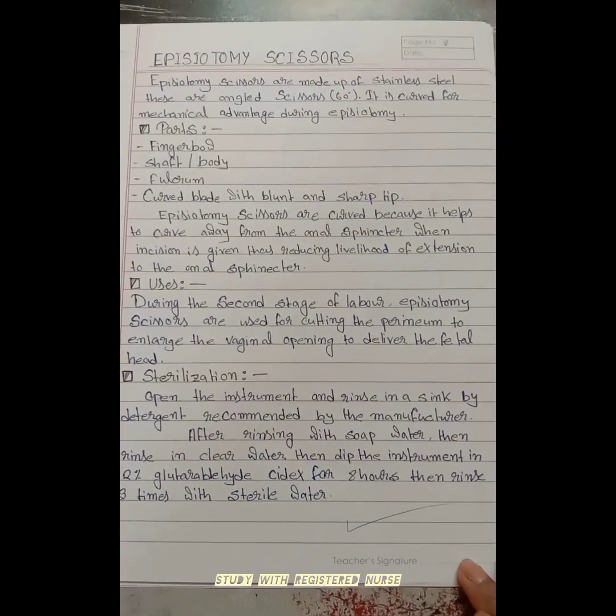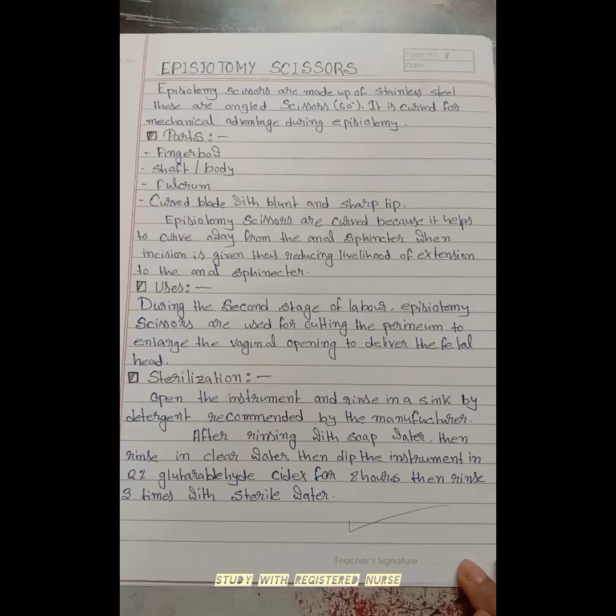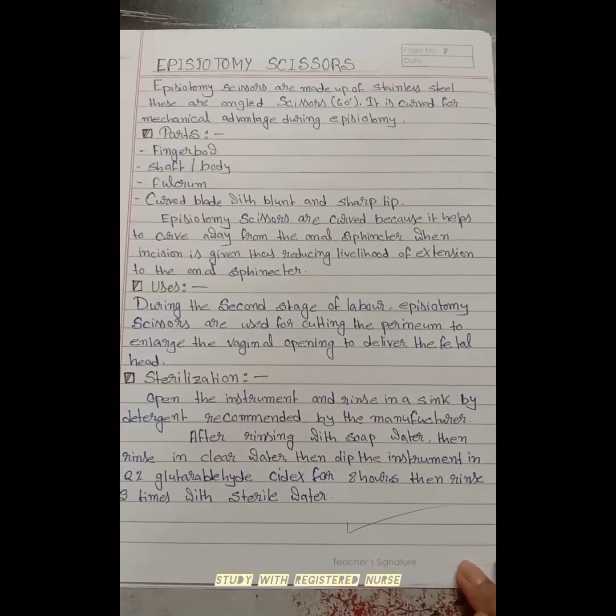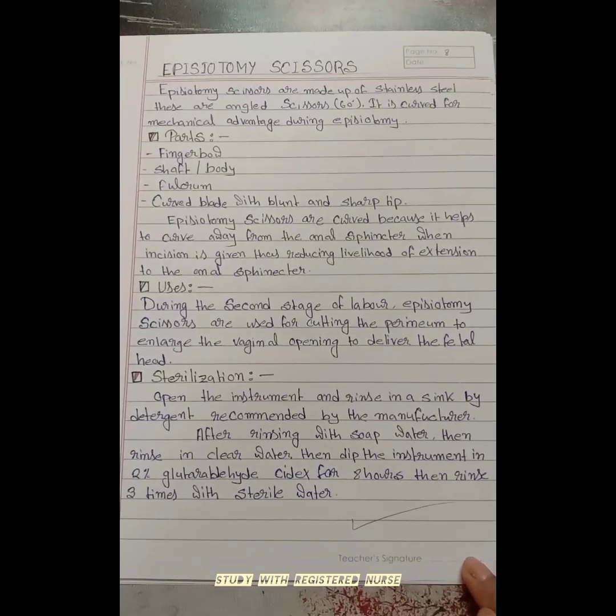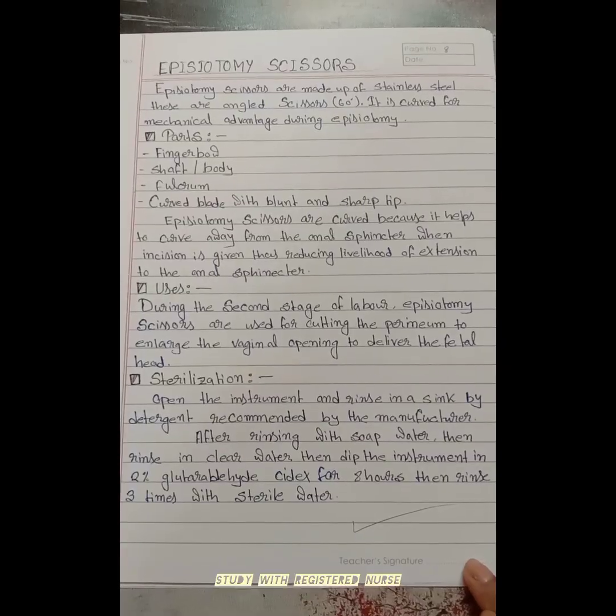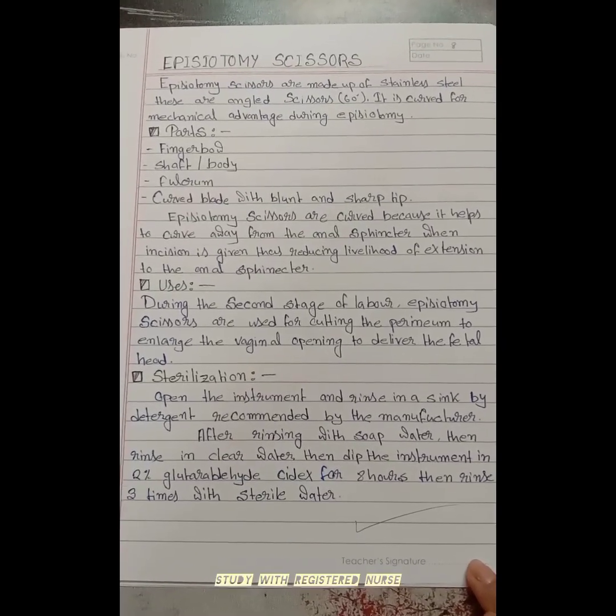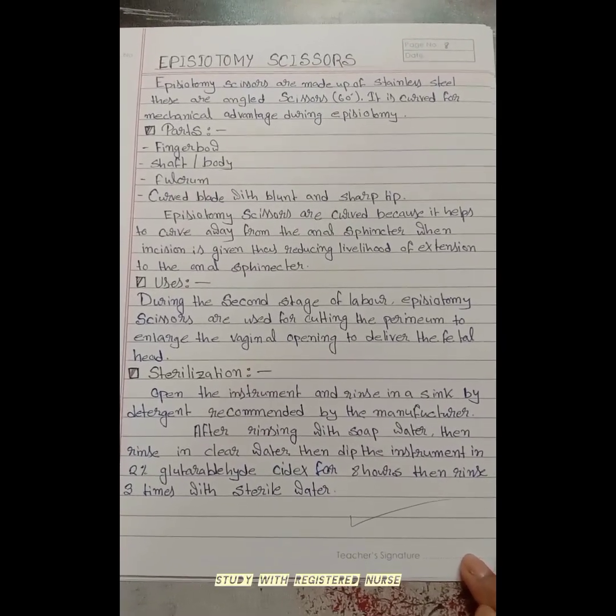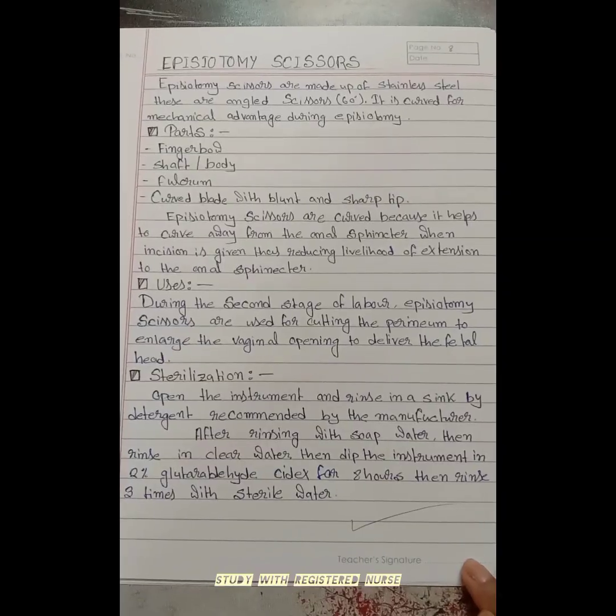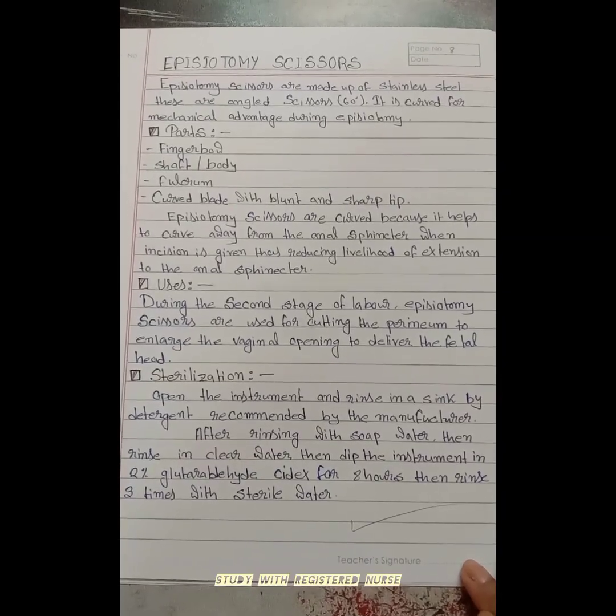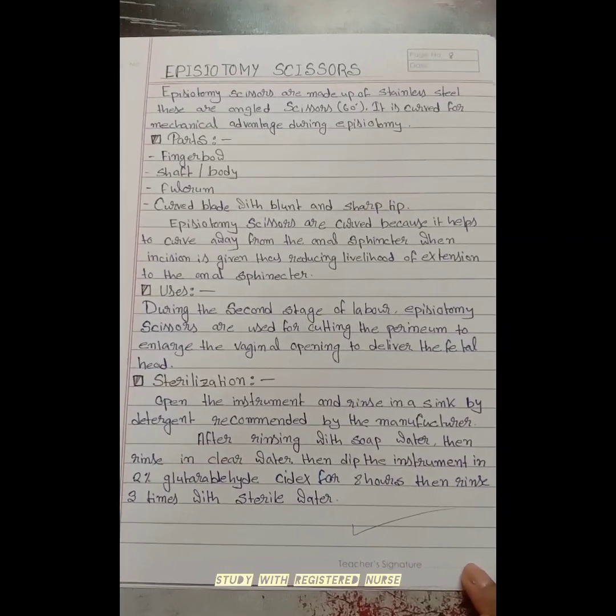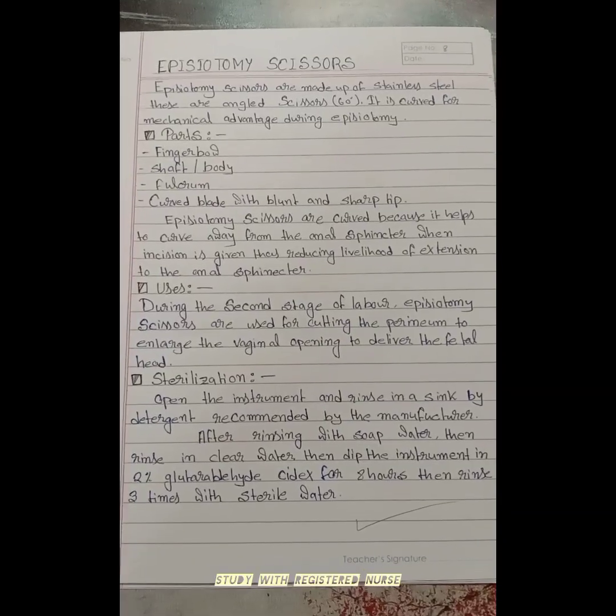Then I discuss the sterilization process. At first, wash with detergent recommended by the manufacturer. After that, wash with normal water, then soap water, then dip in 2% glutaraldehyde Cidex for 8 hours, then wash 3 times with sterile water.